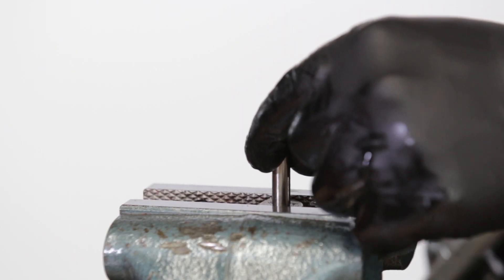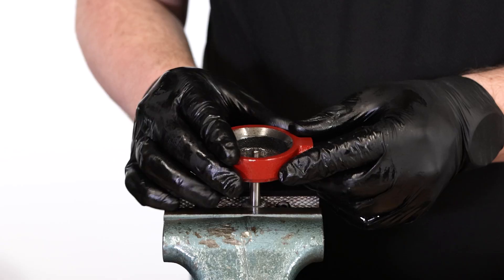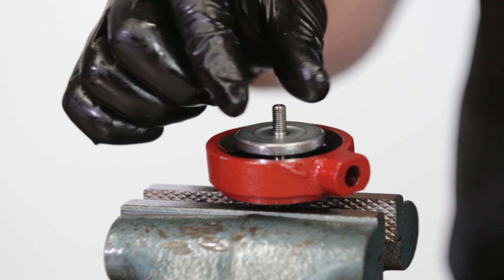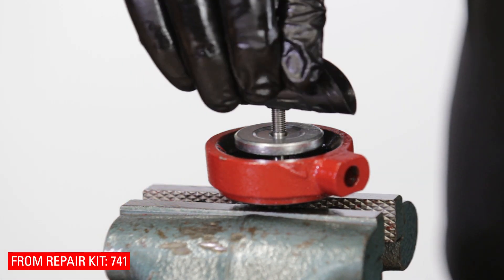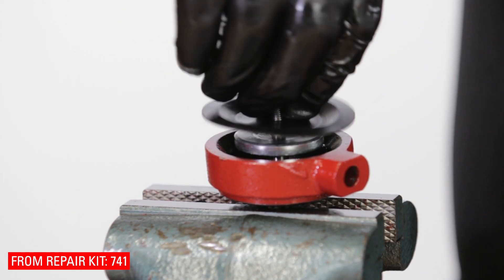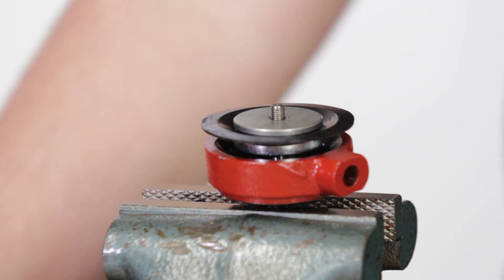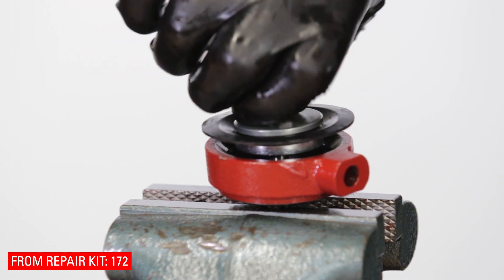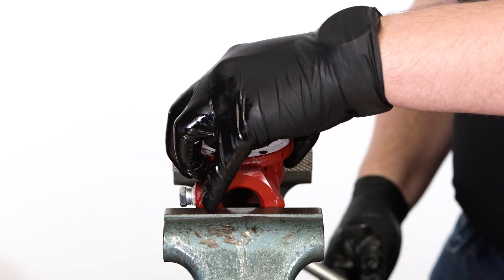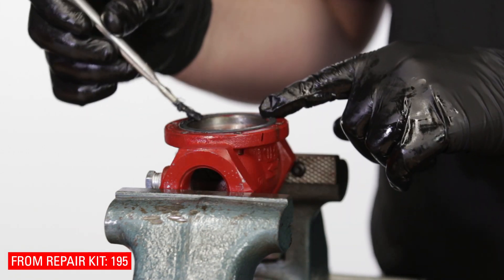Put the stem in the vise, gripping it by the seat disc. Slide the lower housing onto the stem — use a Kimray stem guide if you have one. Slide the 741 upper diaphragm plate onto the stem, part number down. Then add the diaphragm, bevel side down. Add the 731 lower diaphragm plate, part number down. Now thread on the 172 nut. Put the valve body in the vise, then grease the top of the valve body. Place the 195 gasket on top and grease it as well.